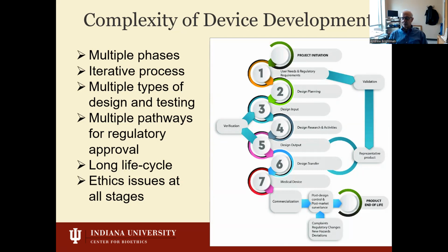Those initial specifications get built into prototypes. The prototypes get tested through multiple iterative processes of design, development, and testing. And when design outputs, the testing of the devices, meets the design inputs, that's called the verification stage. At that point, it can go into the practice of validating whether this device actually solves the user need or the clinical problem. And that validation step is often where the clinical testing or animal testing or human clinical testing come into play. It's not until that point in the regulatory and development pathway that it's considered a medical device and can be submitted for approval for use.